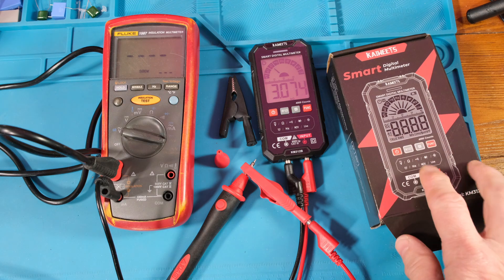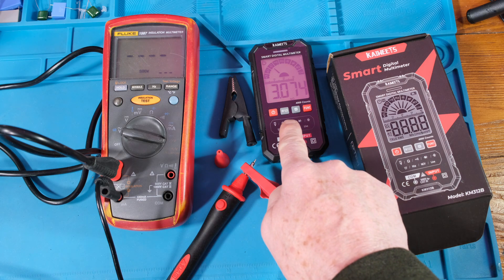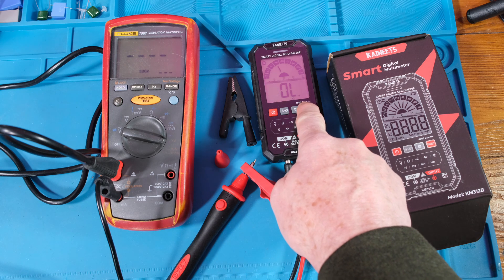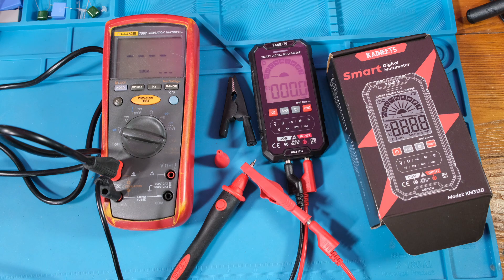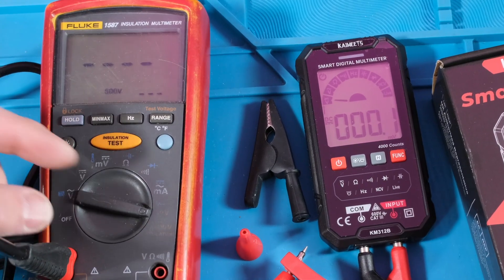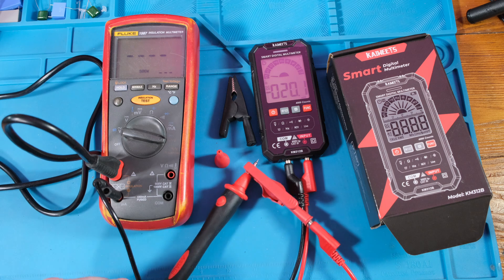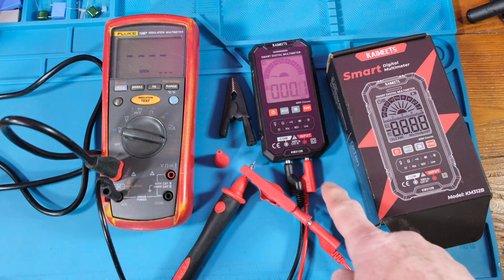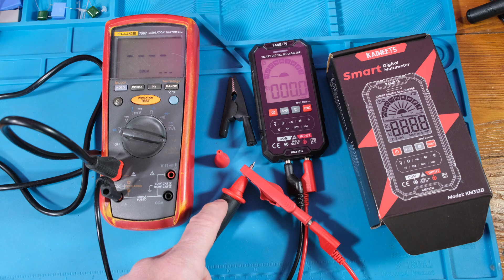We'll start off with the lower-cost Kaimeets smart meter here, the KM 312B. We need to get it into DC volts setting so it doesn't auto-range. We've got the Fluke 1587 insulation meter - this setting here, the last one is for insulation. I've got this fancy new probe - I'll put the link below because I got it at a better price than buying from Fluke. The negative lead is going directly in the meter and the plus is going to the fancy probe that has a button.